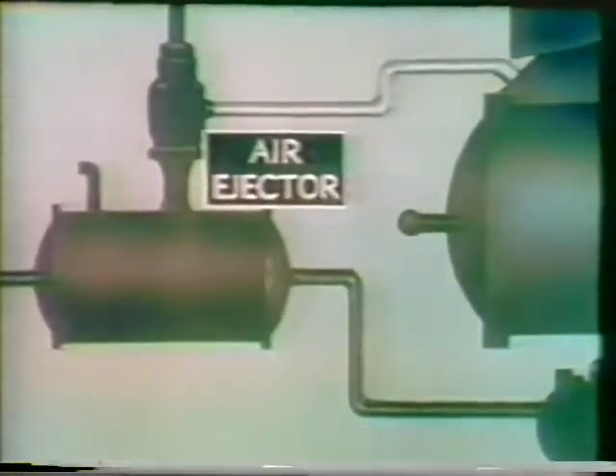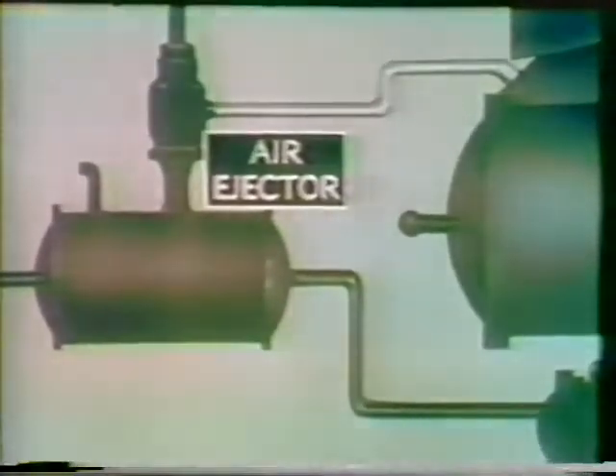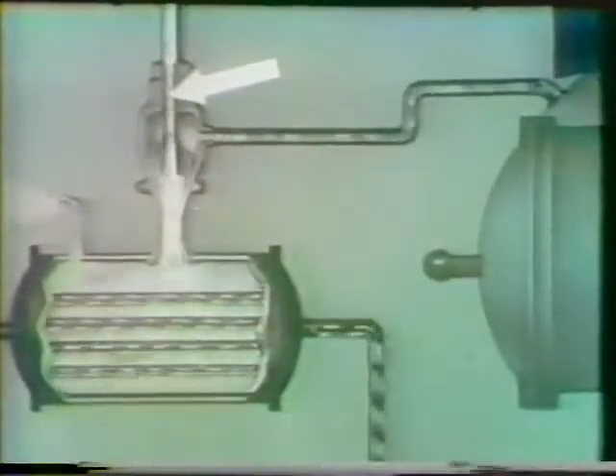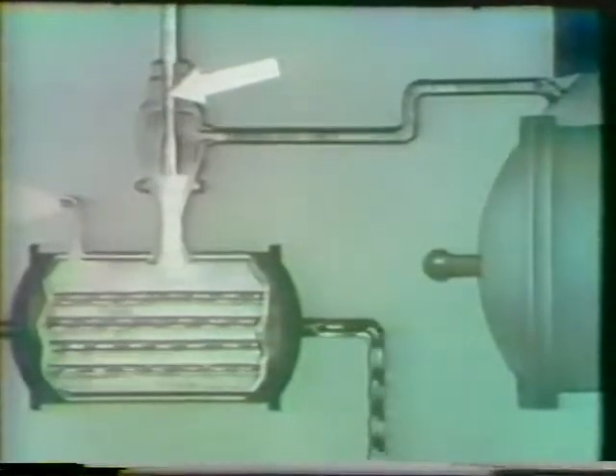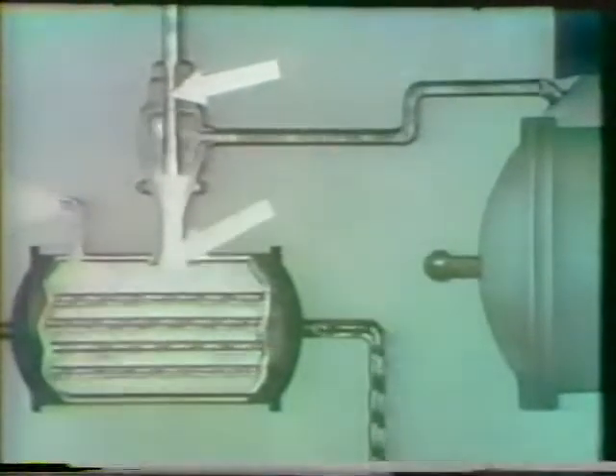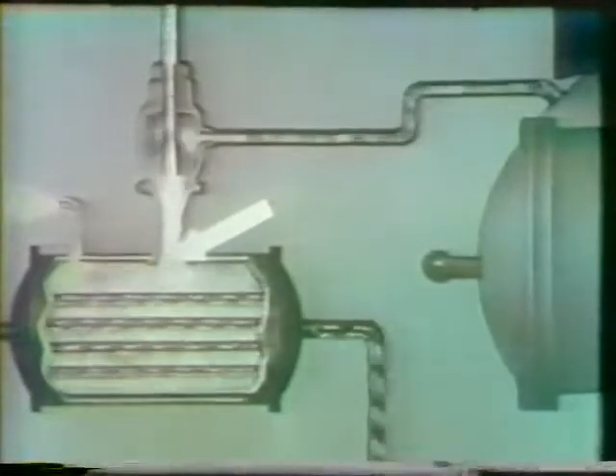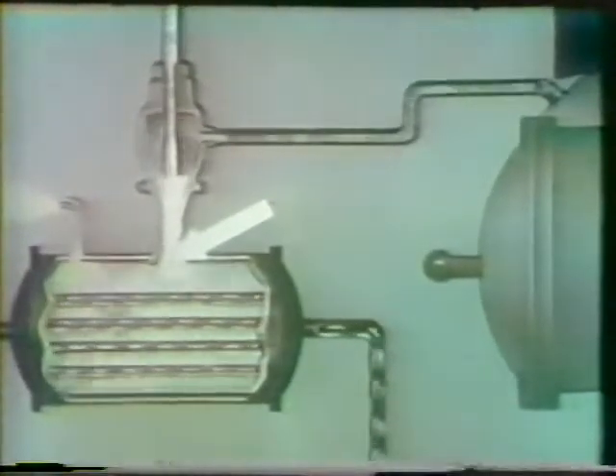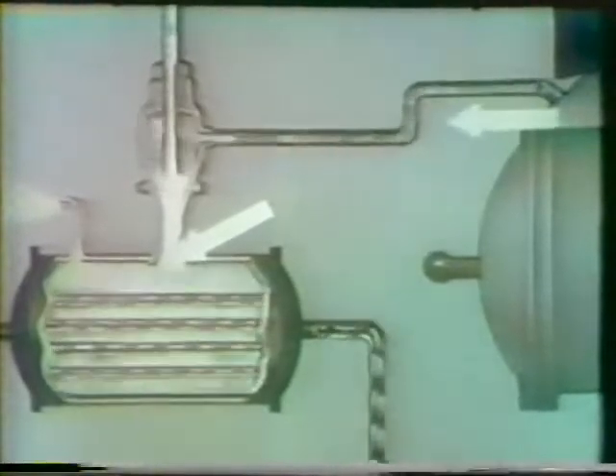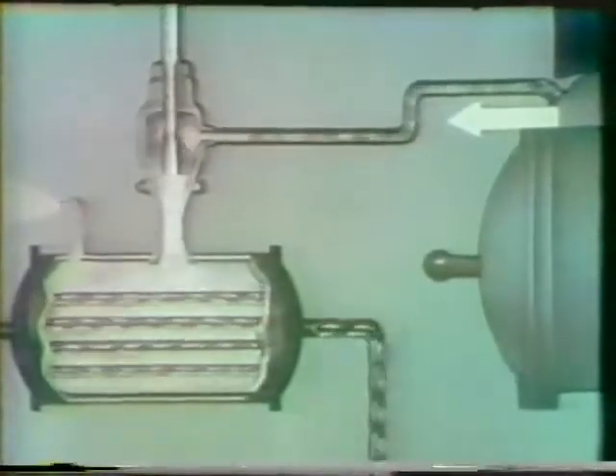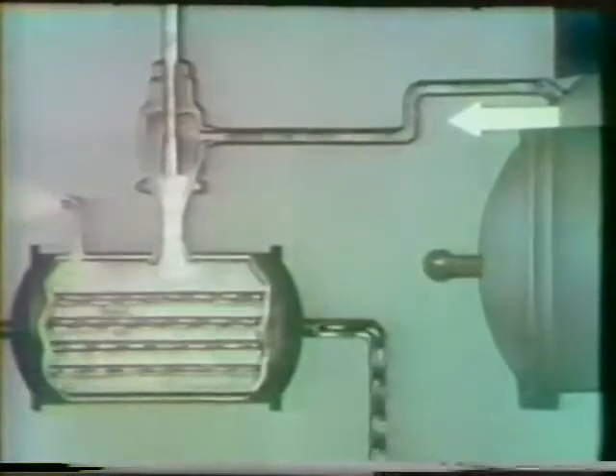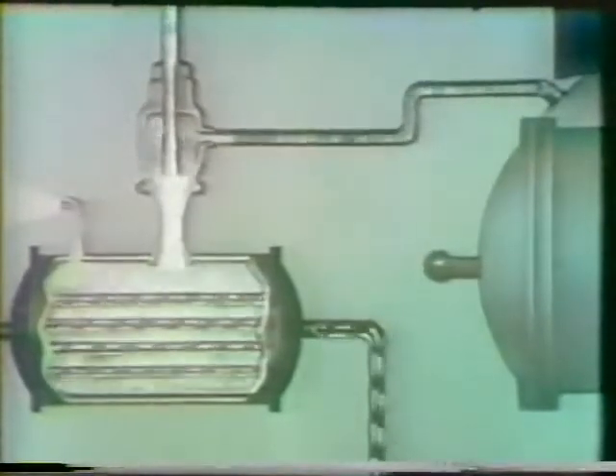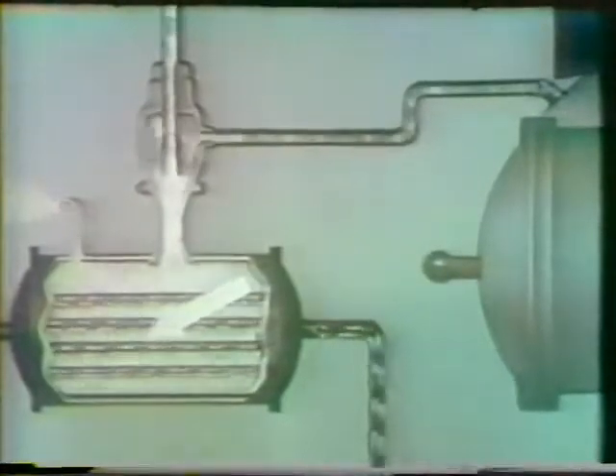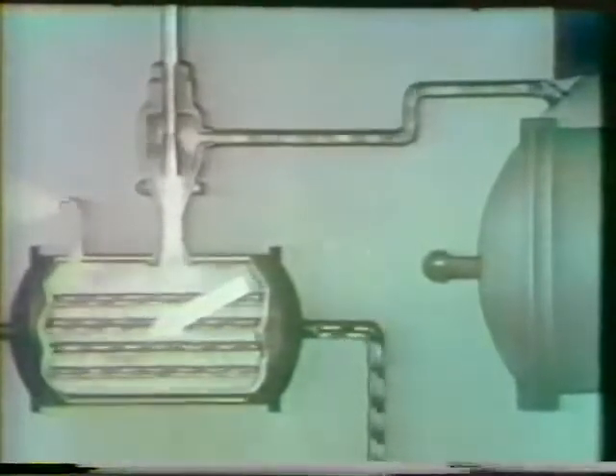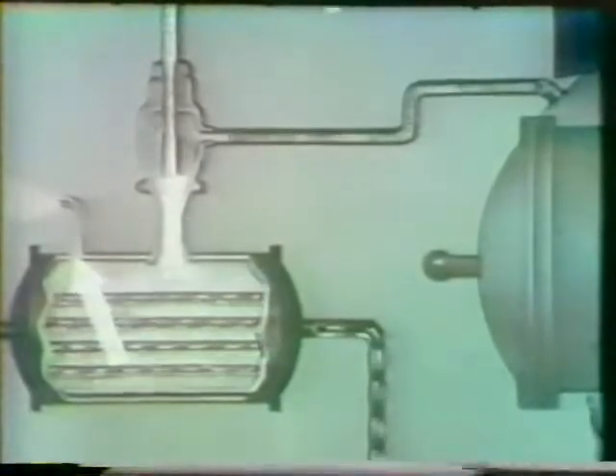Air is removed from the condenser by a steam jet pump called an air ejector. Steam from the auxiliary line is fed through a nozzle, which causes a loss in pressure and a consequent gain in velocity. The steam jet carries along the surrounding air, establishing a vacuum which draws air out of the condenser. The mixed air and steam pass through the air ejector condenser, where the steam is condensed into water and the air is discharged to the atmosphere.